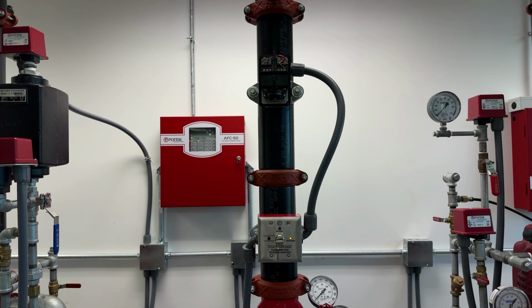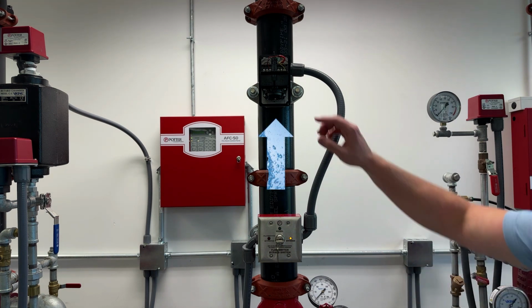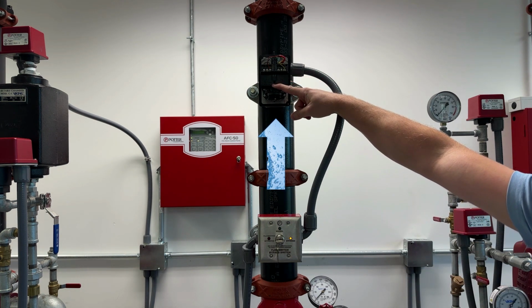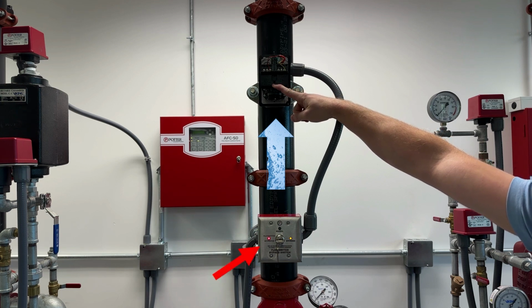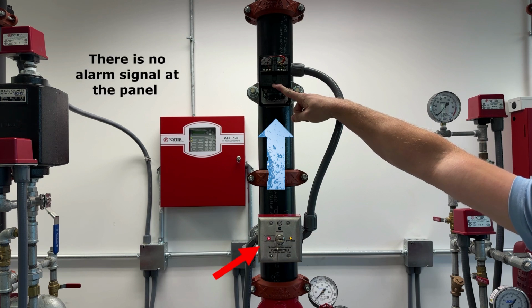Once the flow switch has been bypassed, it is safe to perform maintenance or fill the sprinkler system without activating the flow switch alarm signal. While filling the fire sprinkler system, you will notice that the flow switch will still activate and signal, as shown by the red LED on the FSBS. However, the signal will be intercepted by the FSBS and the alarm control panel will not activate.